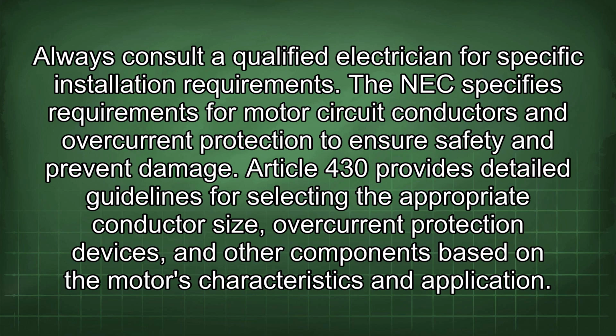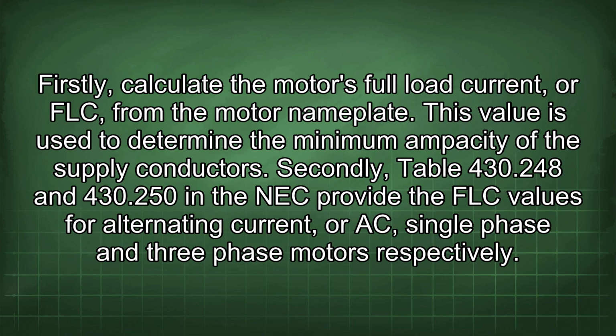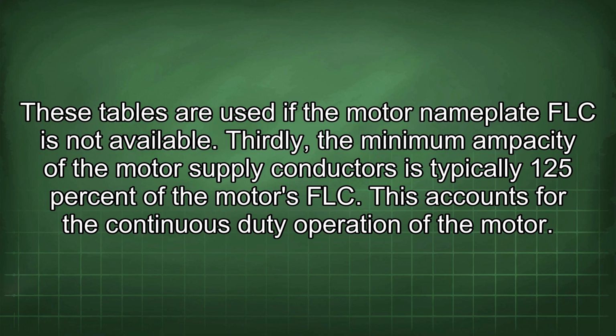Article 430 provides detailed guidelines for selecting the appropriate conductor size, overcurrent protection devices, and other components based on the motor's characteristics and application. Firstly, calculate the motor's full load current, or FLC, from the motor nameplate. This value is used to determine the minimum ampacity of the supply conductors. Secondly, Table 430.248 and 430.250 in the NEC provide the FLC values for alternating current, or AC, single-phase and three-phase motors respectively. These tables are used if the motor nameplate FLC is not available. Thirdly, the minimum ampacity of the motor supply conductors is typically 125% of the motor's FLC. This accounts for the continuous duty operation of the motor.